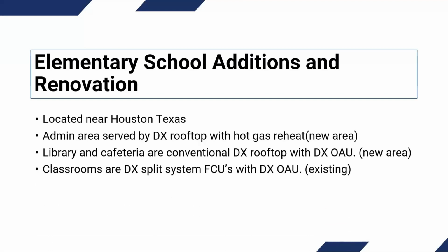The renovation were all the classrooms, which were DX split system fan coil units with DX outside air units serving the outside air for all the fan coil units. The building EMS on this project was very limited. It was, for all intents and purposes, a glorified time clock. It just enabled and disabled based on occupancy. The controls were all internal to the equipment. We did have some ability to change set points for room set points. We added some ability to get some data back from equipment later on.